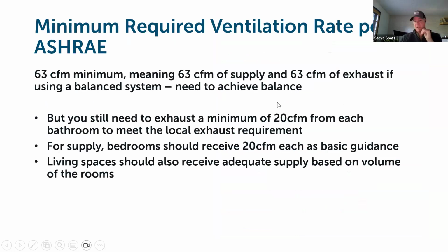So what that means is that, as again, this is a balanced system, you're going to be looking for equipment that's going to be providing 63 CFM of both supply and exhaust. So it's just an equalized volume of air on both sides of the equation moving through the building. So in order to meet the local ventilation requirement in the code, you need to have that 20 CFM if you're going to run the system continuously coming from each of the bathrooms. And in this scenario, we have 2.5 baths. And then for supply side of the equation, best practice is considered to be supplying 15 to 20 CFM of supply air to each of the bedrooms and primary living space.